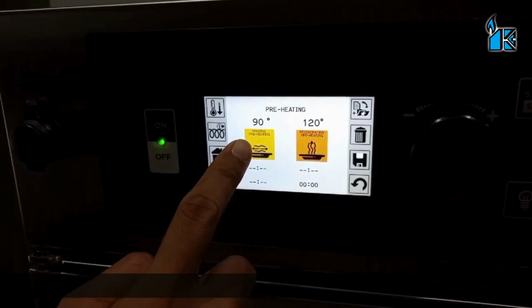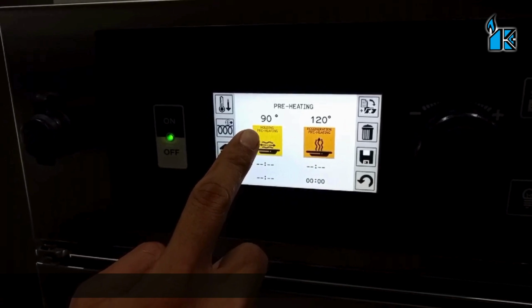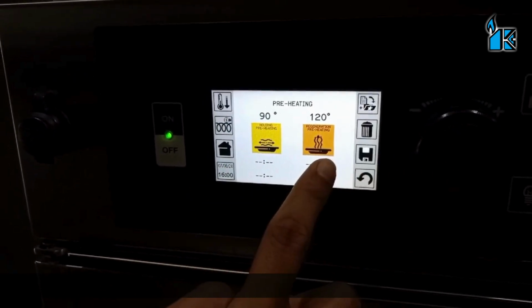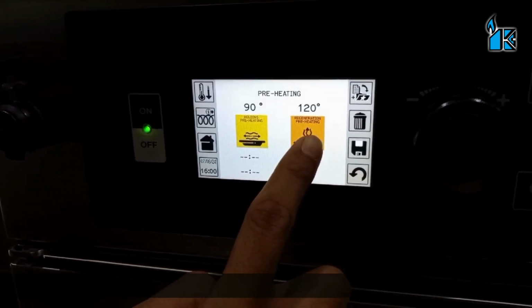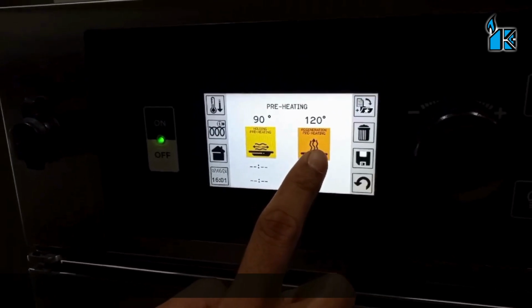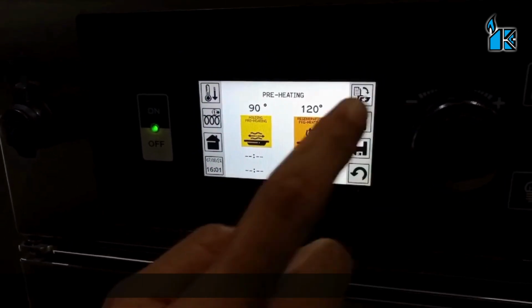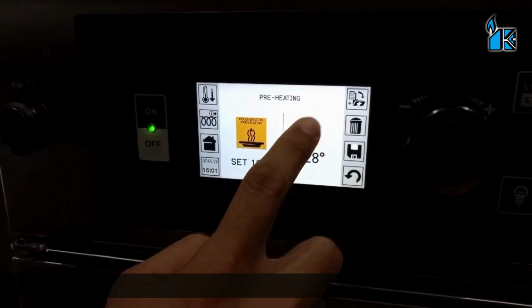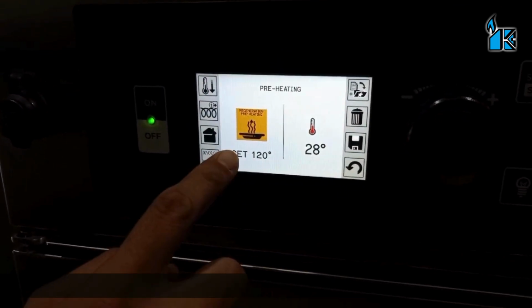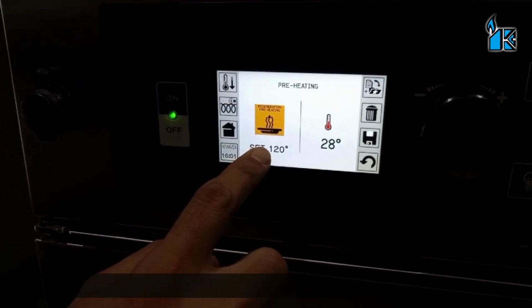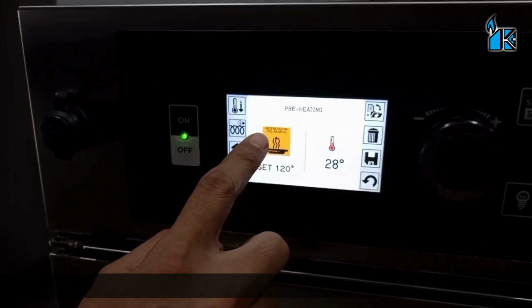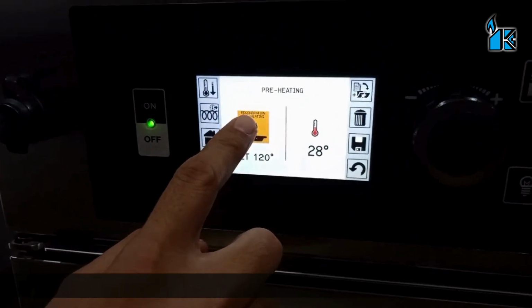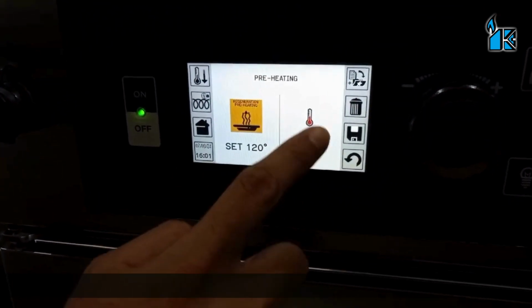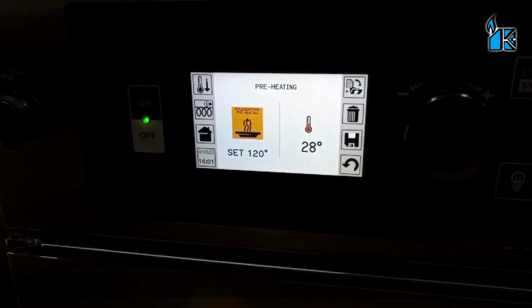Holding preheating is set at 90 degrees Celsius. For regeneration, the product is recommended to preheat up to 120 degrees Celsius. Once you press this, it will show that it has been set to 120 degrees for regeneration preheating, and this is the actual current temperature.